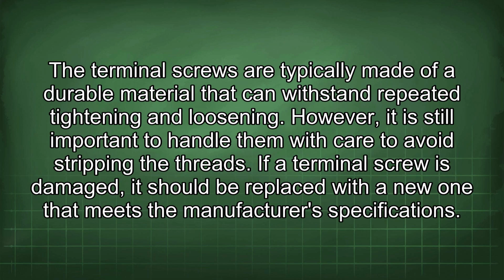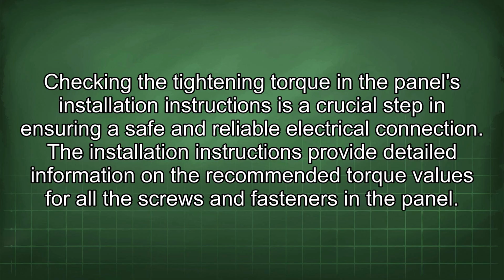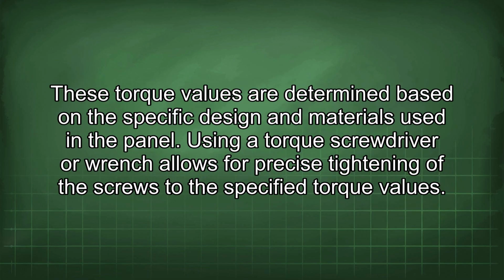The terminal screws are typically made of a durable material that can withstand repeated tightening and loosening. However, it is still important to handle them with care to avoid stripping the threads. If a terminal screw is damaged, it should be replaced with a new one that meets the manufacturer's specifications. Checking the tightening torque in the panel's installation instructions is a crucial step in ensuring a safe and reliable electrical connection. The installation instructions provide detailed information on the recommended torque values for all the screws and fasteners in the panel. These torque values are determined based on the specific design and materials used in the panel.